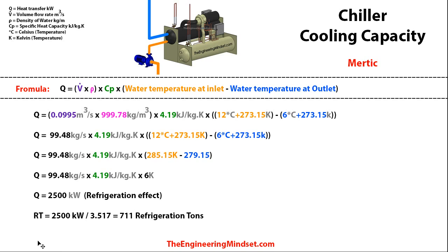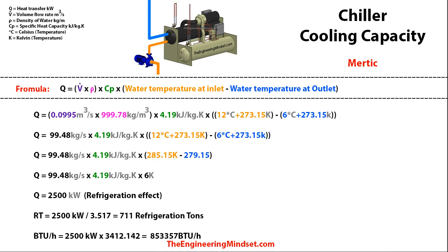If you want to convert to refrigeration tons, divide your kilowatts by 3.517 to give you 711 refrigeration tons. And if you want to convert kilowatts into British thermal units per hour, multiply the kilowatts by 3,412.142 to get your BTUs per hour.